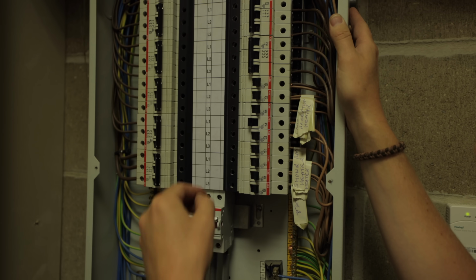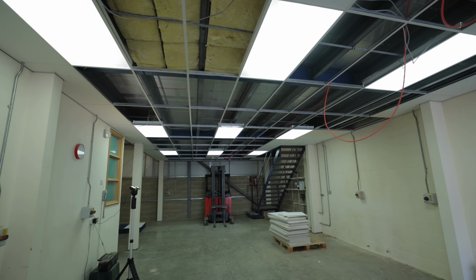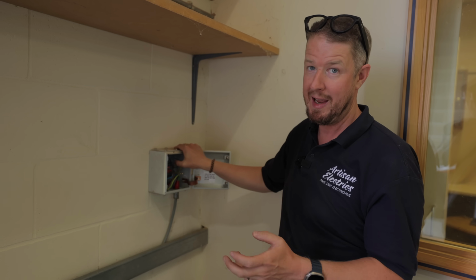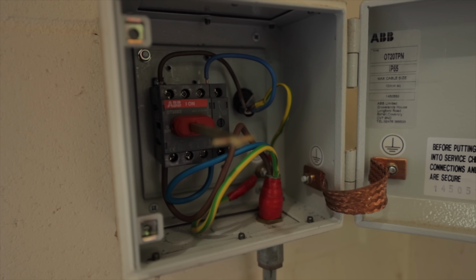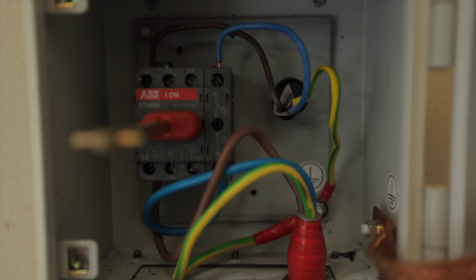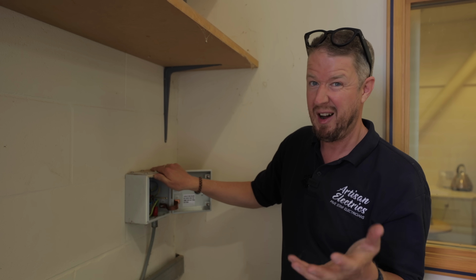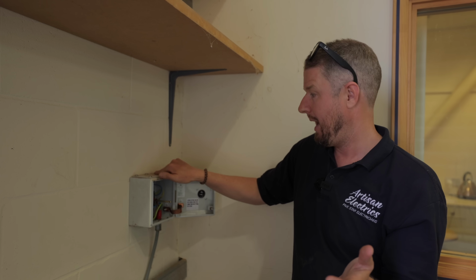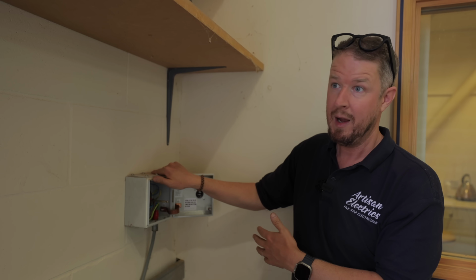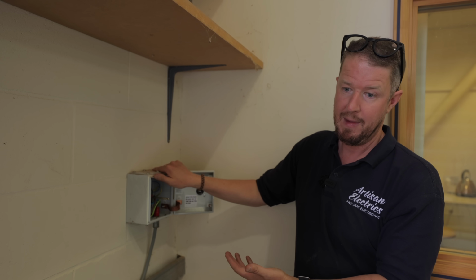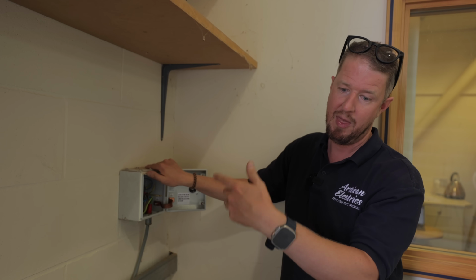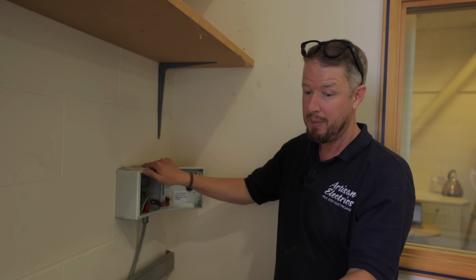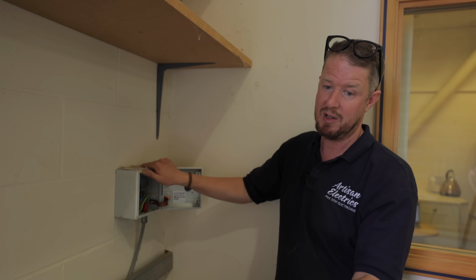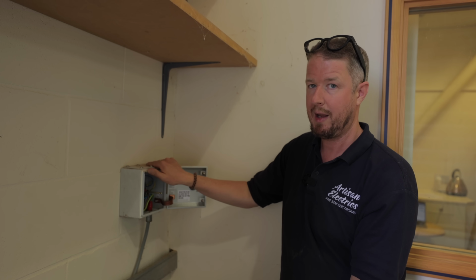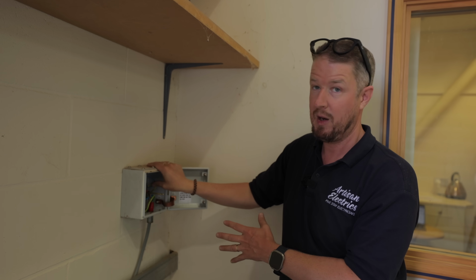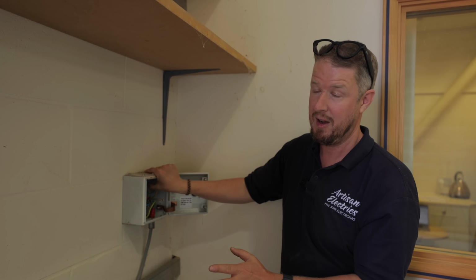Perfect. Now this is a major C2, what we call potentially dangerous in the world of coding on EICRs. So this forklift charger circuit has been wired in 2.5mm twin and earth cable that's only rated at about 25 to 30 amps, and it's on a 40 amp circuit breaker. So it's overrated. Now it's on a 32 amp commando socket there, so in theory it shouldn't pull more than 32 amps. I'm going to look at the data plate on the side of the charger to see how much wattage it actually pulls to work out the amperage, but I'm not happy with the fact that it's only wired in 2.5, so we are going to have to rewire this circuit, unfortunately.